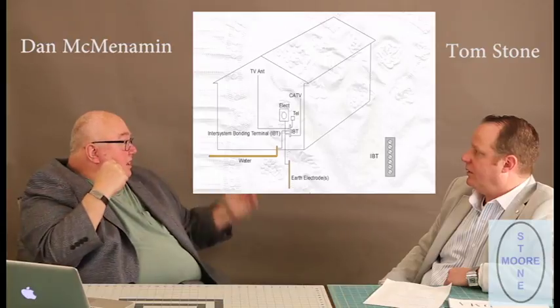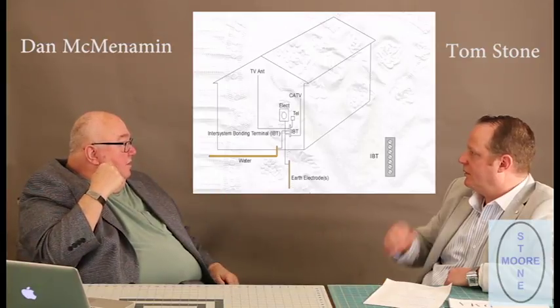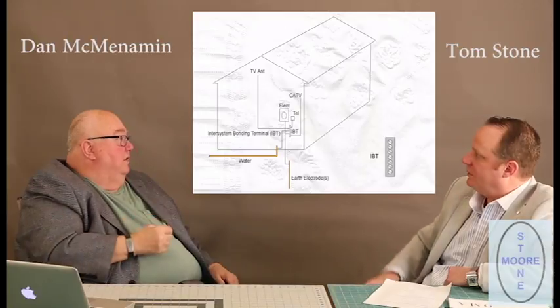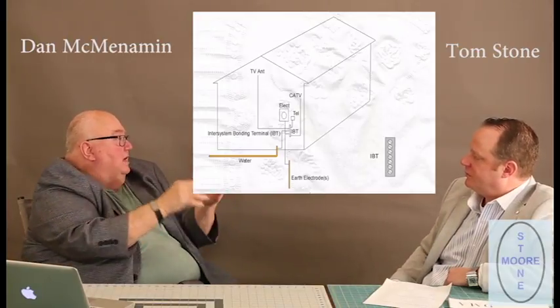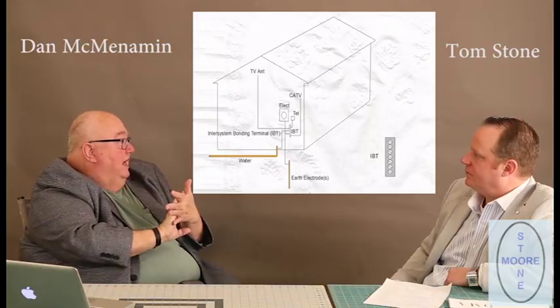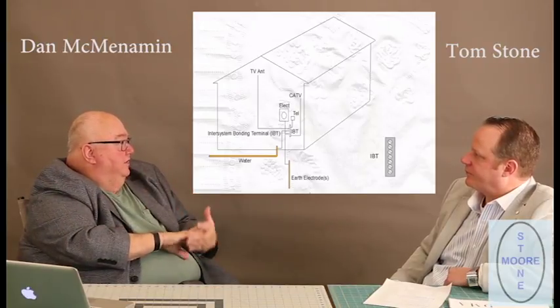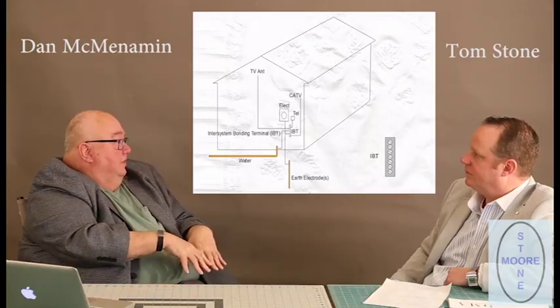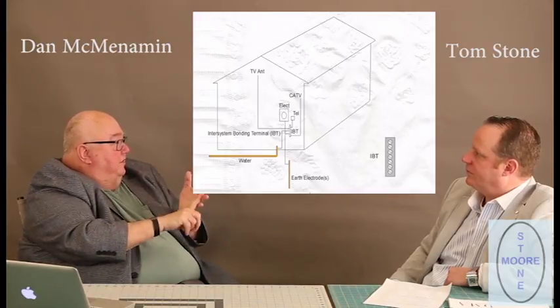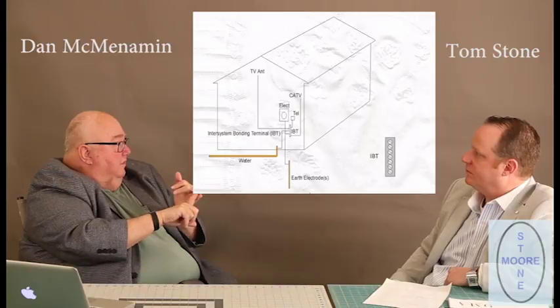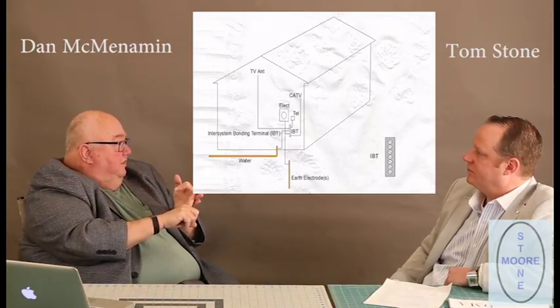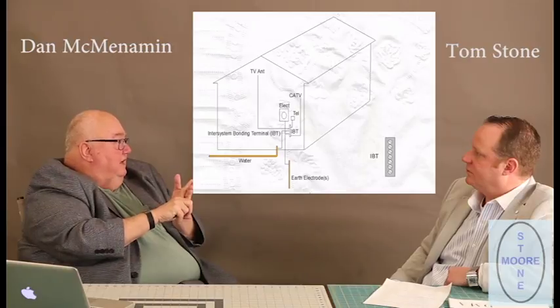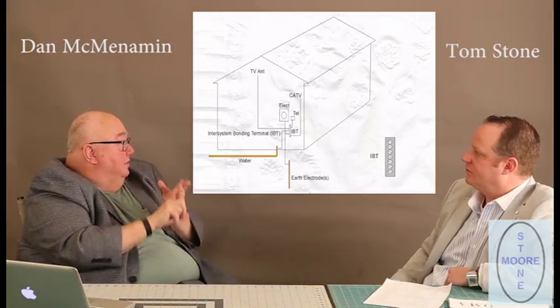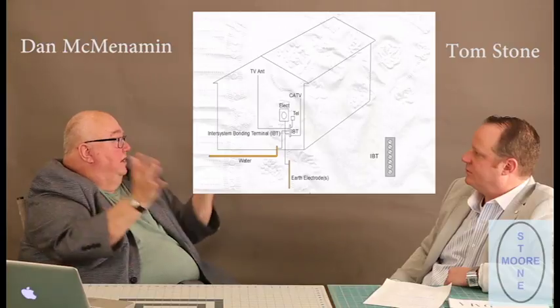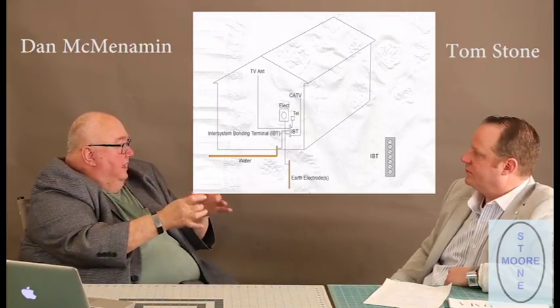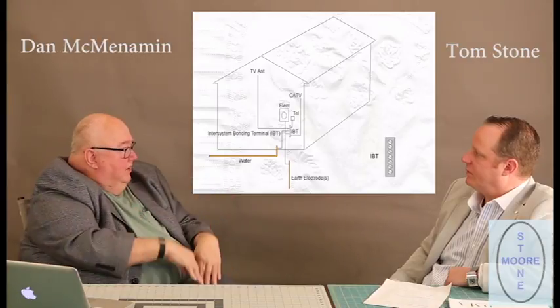All right, so you don't want somebody on the phone and the electric line takes a lightning hit, and you've got maybe a bunch of voltage in there that could hurt somebody. Exactly. Or cable TV or any of those things. So all of those items, water pipe if it's coming in a metallic pipe, ground rod or rods, they all become your electrodes, earthing electrodes. And then your electric service, your telephone service, your cable TV service, if you have that, or if you have a TV antenna mast or a CB radio or some kind of ham radio mast, any of these things, they all get bonded together at that inter-system bonding terminal and go to ground.